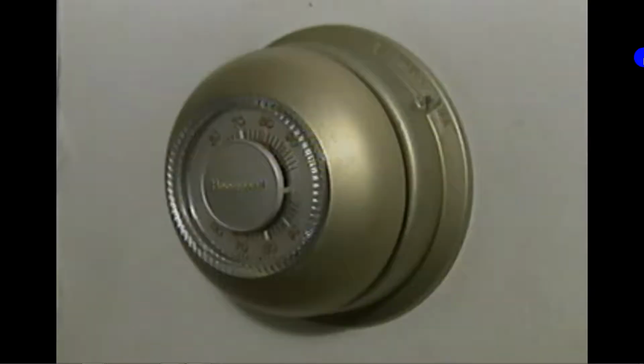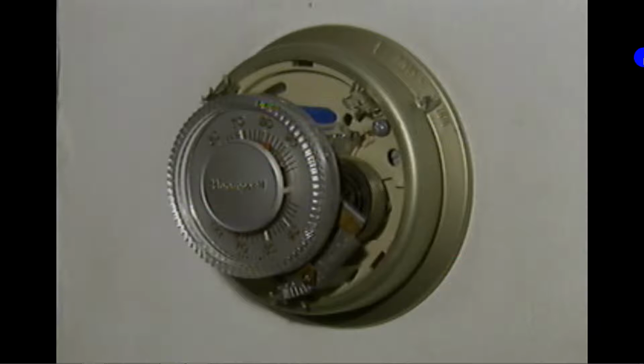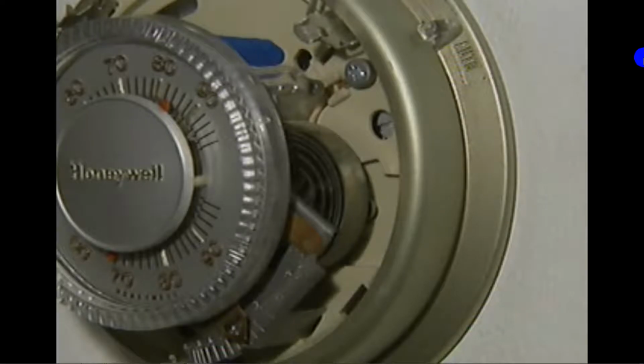Another commonly used type of pilot device is a thermostat. Thermostats are devices that sense changes in temperature. Thermostats can be used to open or close circuits when temperature reaches a preset point. Two common types of thermostats are the bellows type and the bimetallic strip type. In contrast to a bellows thermostat, which may have its sensing bulb located some distance away from the contacts, a typical bimetallic thermostat is located close to the contacts it operates, and it senses temperature at that location.